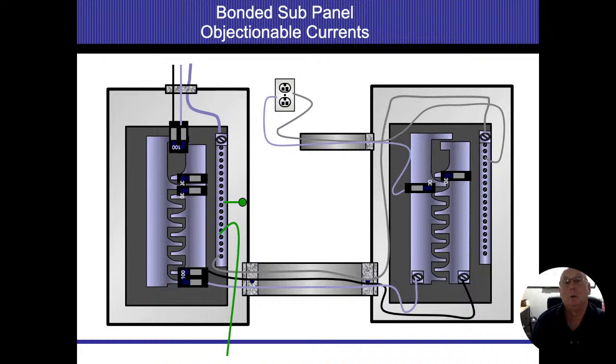So now what we do is we're going to throw a bond on the sub panel. And again, this is under normal circumstances. So we're going to energize that outlet again, so we're going to be doing work. Amperage does not disappear. So we're going to energize our energized conductor, and then amperage will be on the neutral. Amperage or electricity is going to flow in any means possible. So yes, it is going to flow on the neutral.